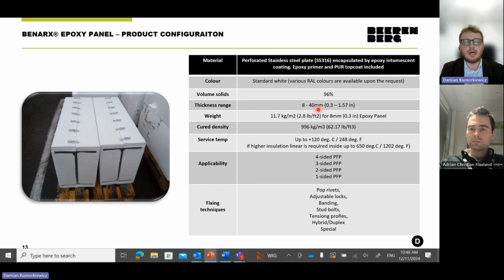However, we would like to show you our case studies from previous projects and give you a better insight into our system. So this is the Benarx Epoxy Panel. It is made from a perforated stainless steel 316 plate, which is acid-proof, and it is covered with epoxy intumescent coating both outside and inside. We also applied an epoxy primer and polyurethane top coat on top of that. Our standard color is white, but we can paint it in any color. The thickness range depends on the PFP rating, but it varies from 8 up to 40 millimeters for the toughest PFP specifications.